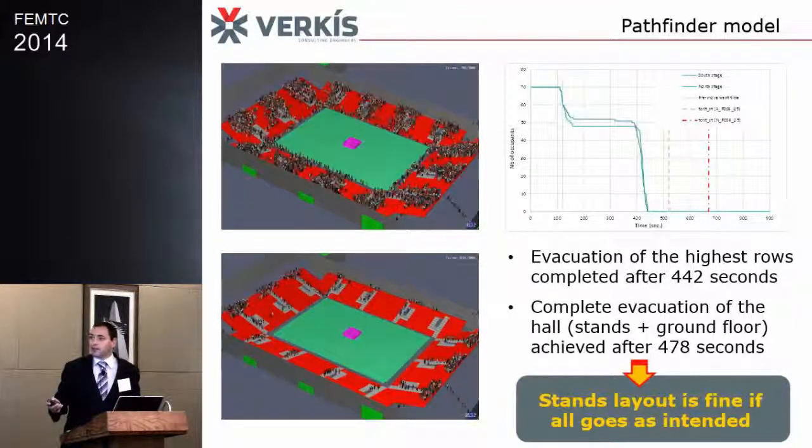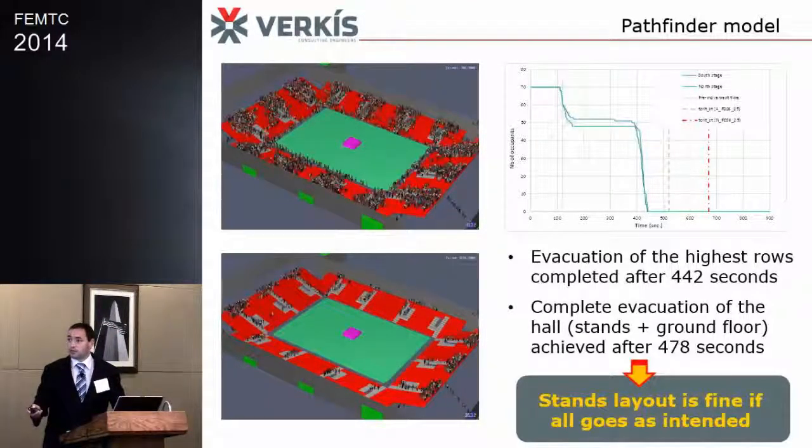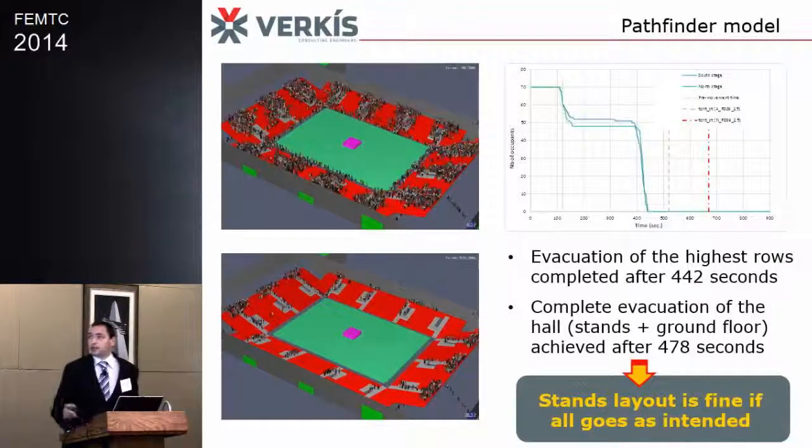People here have to wait before these ones have gone into the stairways and evacuated before they can go down themselves. You can see that even after 6 minutes, this is almost clear, but you still have a few people waiting to get into the stairway and evacuate. We can see it here on this graph.